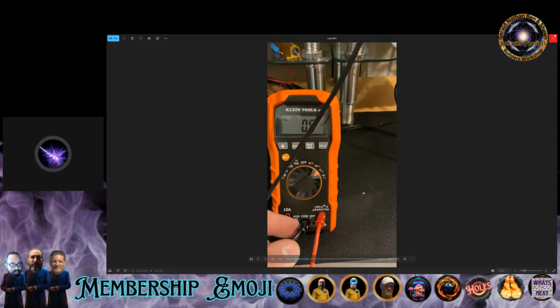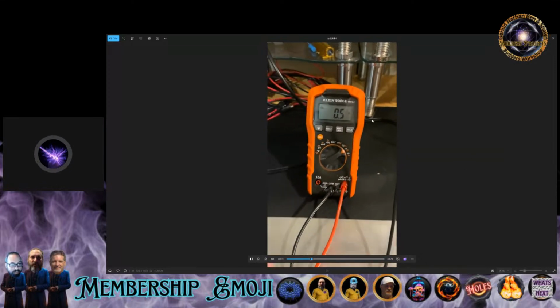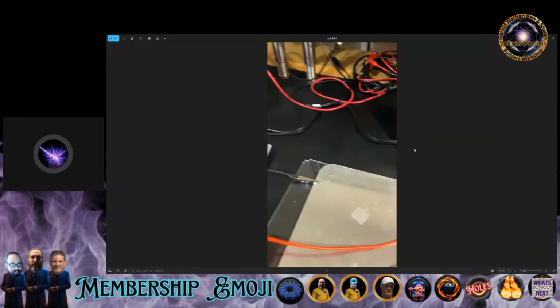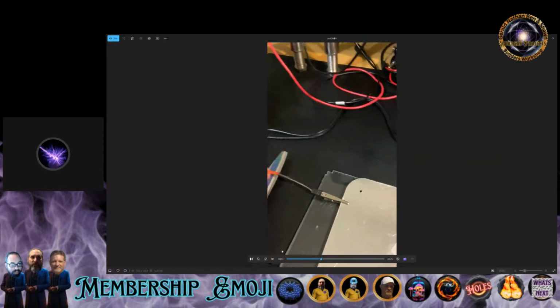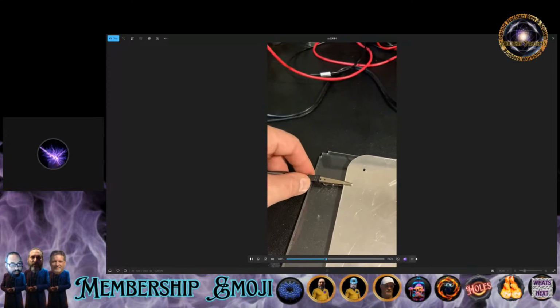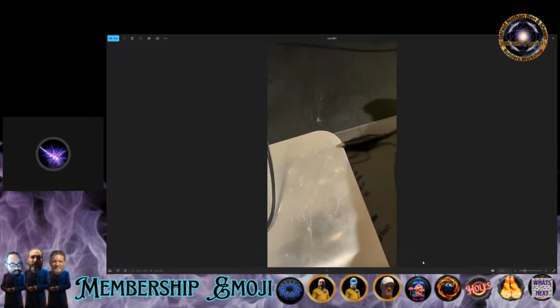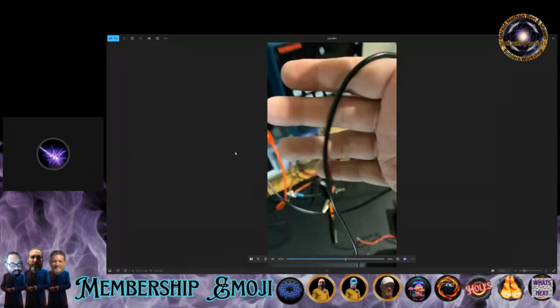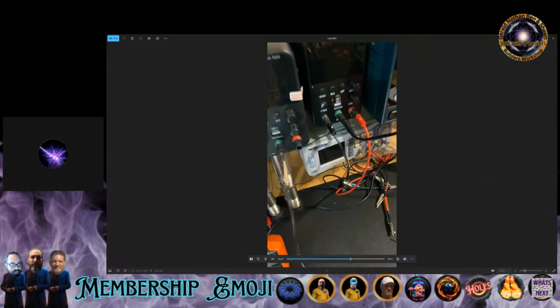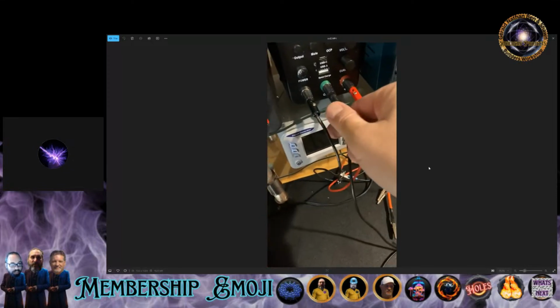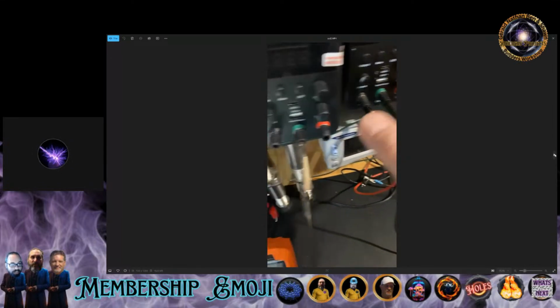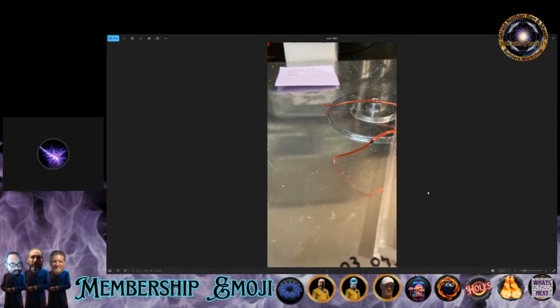Running to the plate, I'm showing that each end of the plate is conductive. There's only 0.5 ohms between the ground and the testing device. From ground to ground, there's 0 ohms. I'm checking it here, each side.